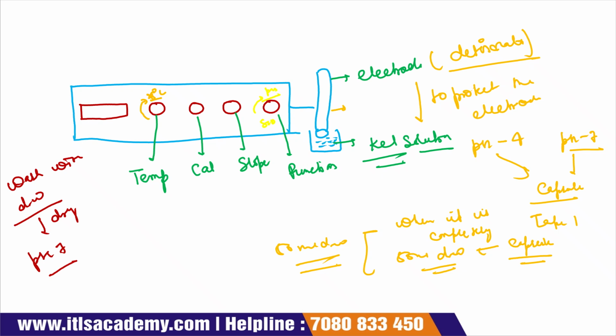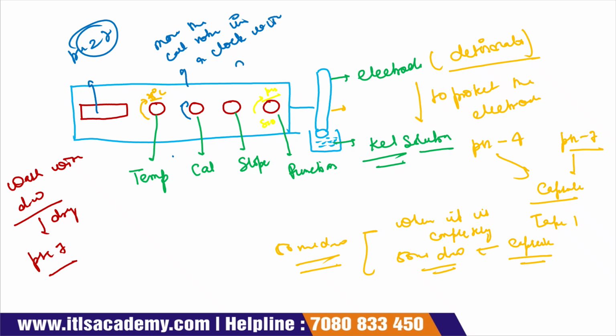Now what you have to do, you have to move the calibration knob in a clockwise direction until the pH reaches 7. Then stop. Again move the knob from pH to standby, and again wash with distilled water, then dry, then measure pH 4. Again move from standby to pH. Here some values are showing.